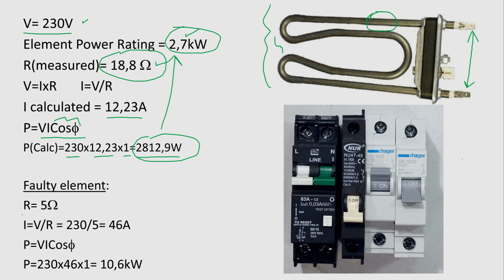Now, if you're doing your resistance measurement between these same terminals and you get 5 ohms or something low like that, now just doing a calculation, if I want to work out the current, it's the voltage divided by the resistance. In this case, it's 46 amps. Now, that is very high current for a domestic dishwasher, and what would happen is it would want to pull such a high current and it would actually trip the overcurrent circuit breaker. Notice that this overcurrent circuit breaker is rated at 20, and 46 amps is very high. Now if you compare it to what it was, it should have been about 12 amps. So we can see that 46 amps is a faulty condition.